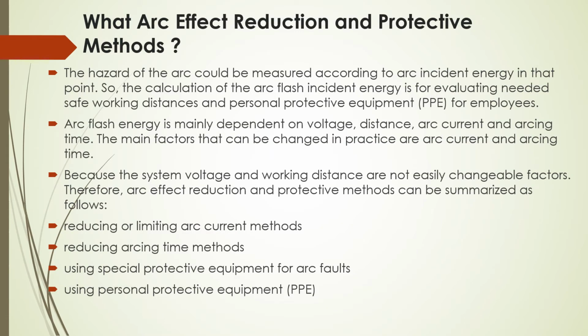What are arc effects reduction and protective methods? The hazard of an arc could be measured according to arc incident energy at that point. So, the calculation of arc flash incident energy is for evaluating needed safe working distance and personal protective equipment for the employees. Arc flash energy is mainly dependent on voltage, distance, arc current and arcing time. The main factors that could be changed in practice are arc current and arcing time. Because the system voltage and working distance are not easily changeable factors, arc effect reduction and protective methods can be summarized as follows: reducing or limiting arc current methods, reducing arcing time methods, using special PPEs for arc faults, using PPEs.